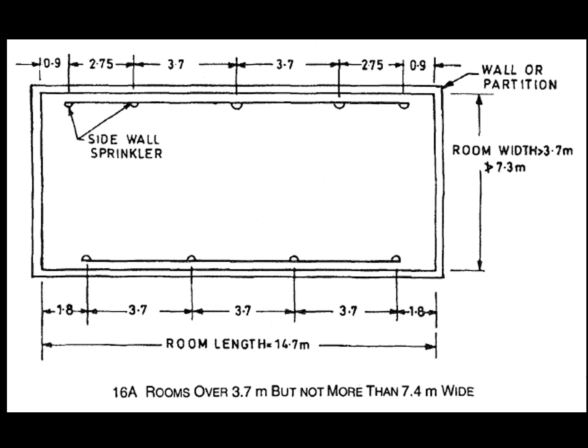Friends, this particular sprinkler diagram is for a rectangular area, the room over 3.7 meter but not more than 7.4 meter wide. In such cases, you have to work out the spacing, equal spacing. So it will be 3.7. Say in a particular case, if the room length is 14.7, it is getting divided into four portions, five portions, three portions of equal length of 3.7, and other two just half of it, not exactly half of it, 1.8 meter this side. Like this, you will have the rows.